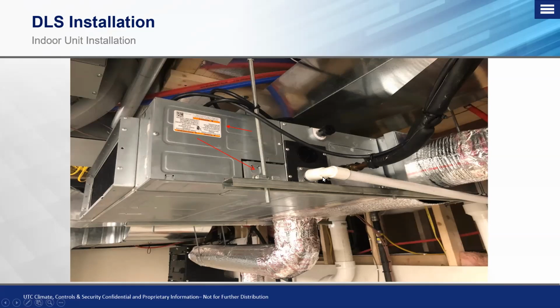Now, the issue with that is that this right here, if it was installed the other way, would have been the drain connection that they needed to hook up to. This one right here is when the unit is installed vertically and we bypass the pump, so we allow only a gravity drain to feed out either to a drainage system or a secondary pump to get that condensate water out of there. Another great indication of when you have a unit installed upside down is you'll hear the fan motor intermittently come in and out of operation, and it's not producing enough CFM to be able to condition the space.